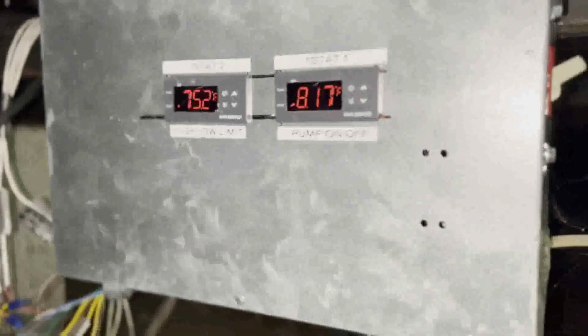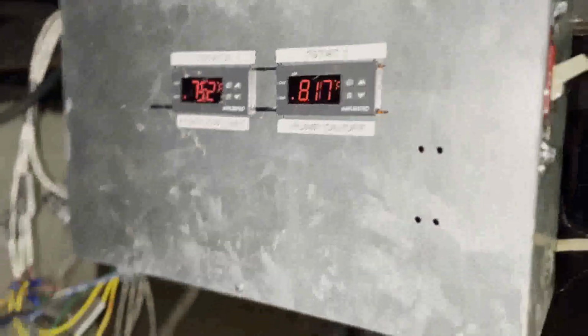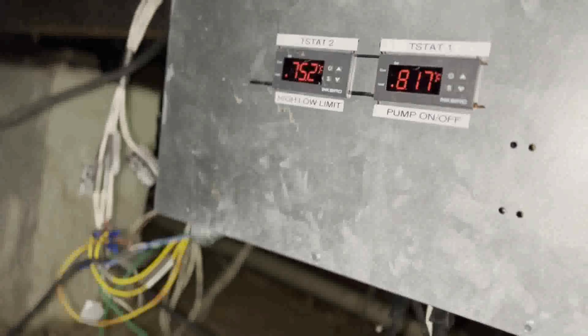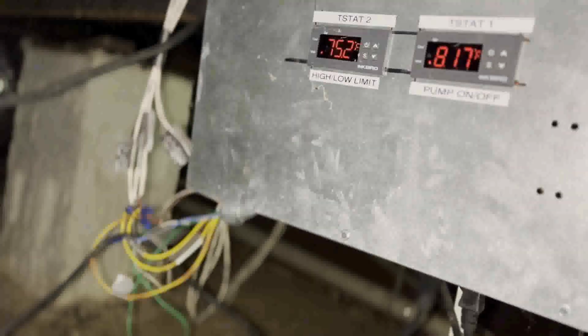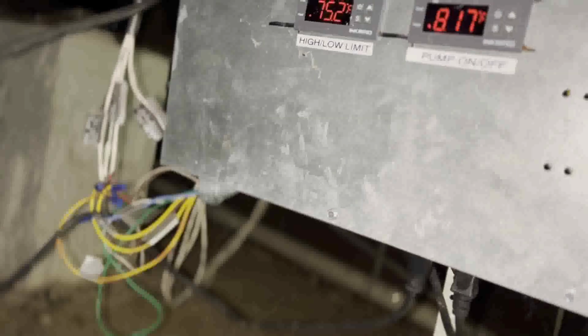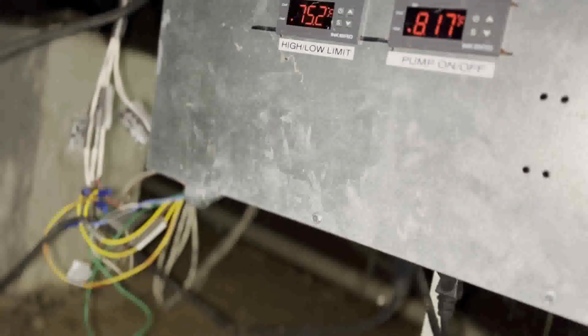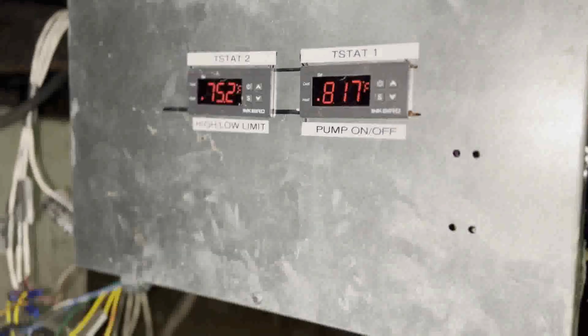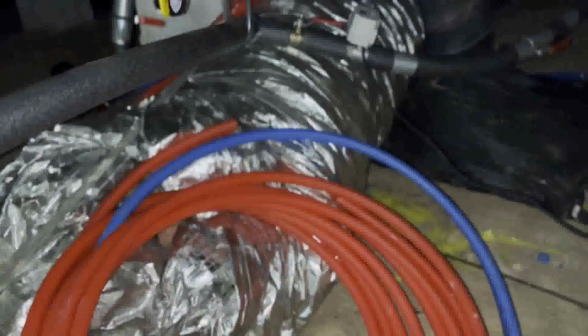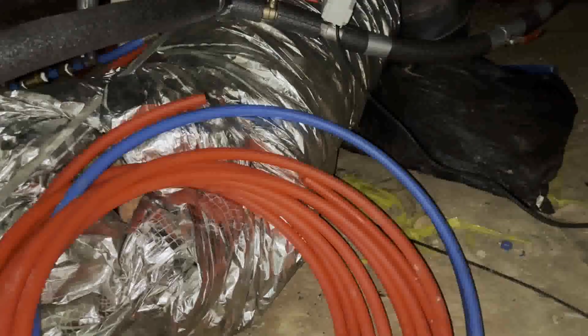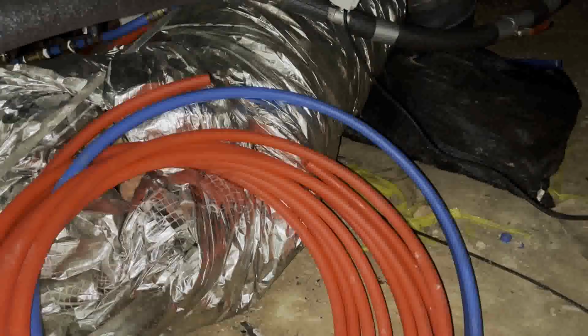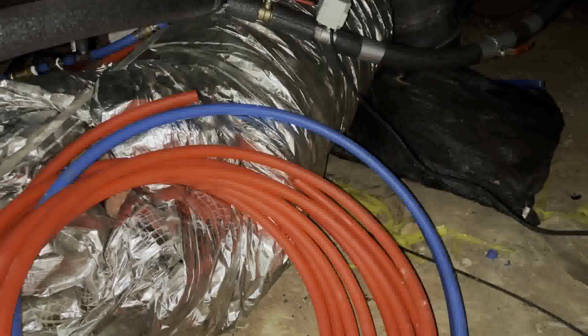I am heating my domestic hot water with this system. So if this water gets really cold, although my heat could run off of 130-degree water, I don't want to run the water that low, because once it gets that cold, I'll actually start taking heat out of my domestic hot water tank. So once the water gets so cold, this turns that off. So all water circulation on this side of the system stops. And if that's happening, that means the boiler has run out of fuel, and it's going to be time to reload.